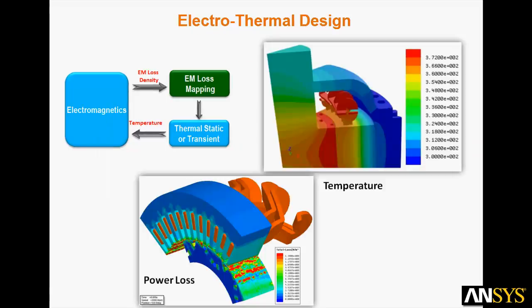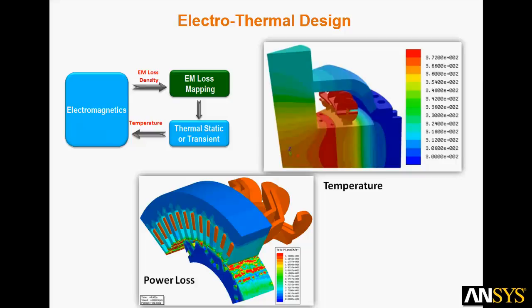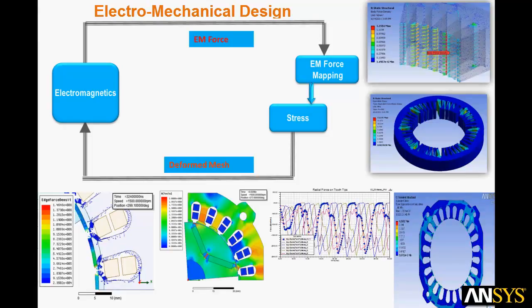The first step is electrothermal design. Maxwell is used to simulate electromagnetic fields and the associated electromagnetic power loss density. Automated routines map these losses to the ANSYS CFD, Computational Fluid Dynamics Solver, for static or transient thermal simulations. The resulting temperatures from the thermal analysis can be passed back to Maxwell to adjust material properties so that additional corrections to the electromagnetic field may be computed.